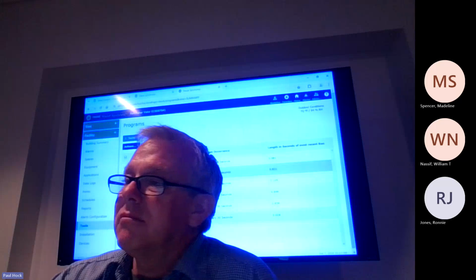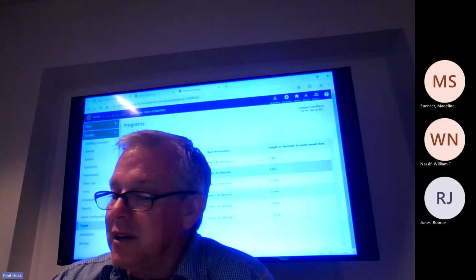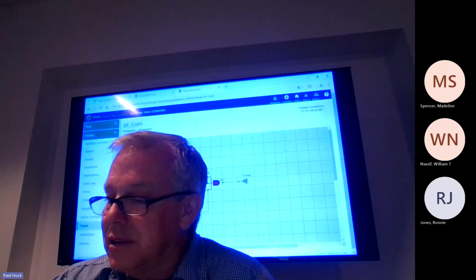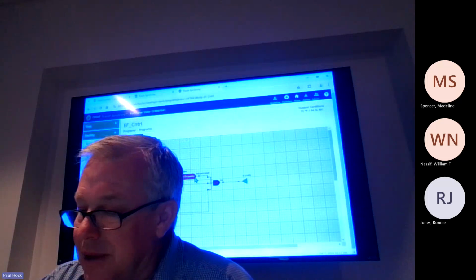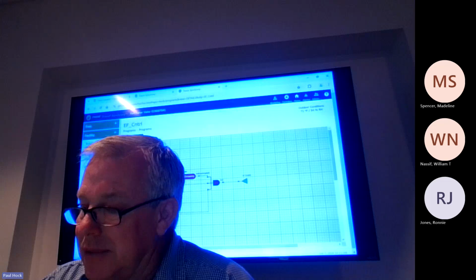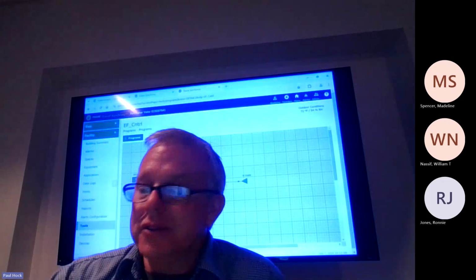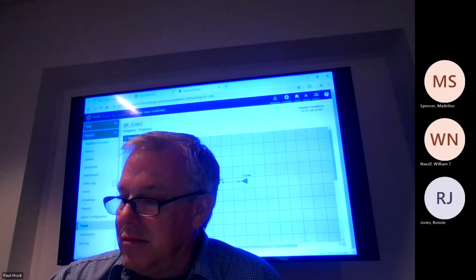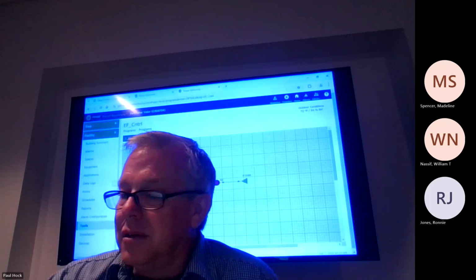Might be another handy thing for us, just something to look at. Exhaust fan control. Occupancy's all good. Exhaust fan dampers false. I've got to look at that. You want to put on 204 exhaust fan damper status? Take a look at that.